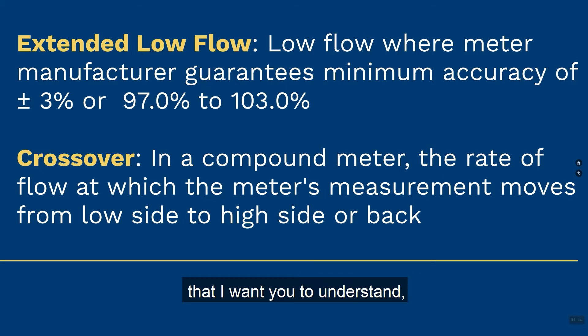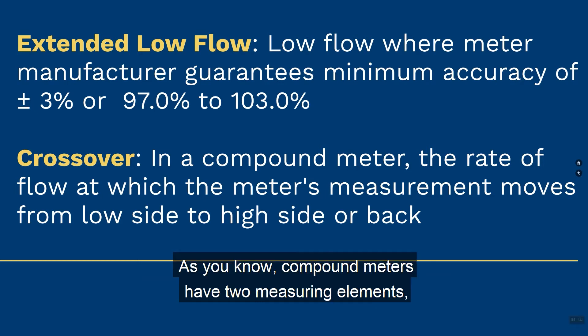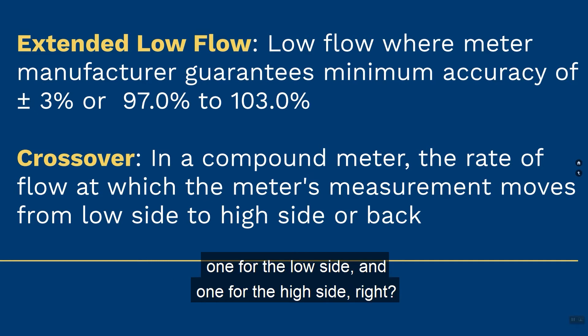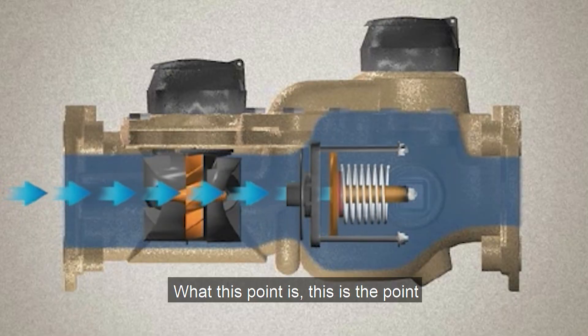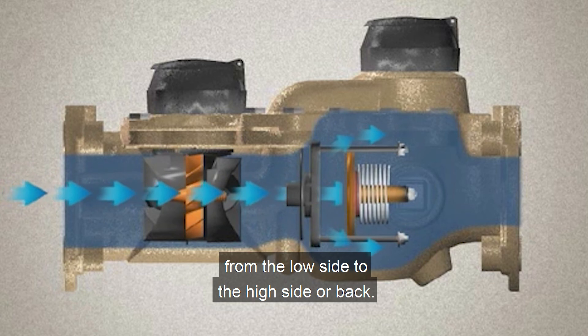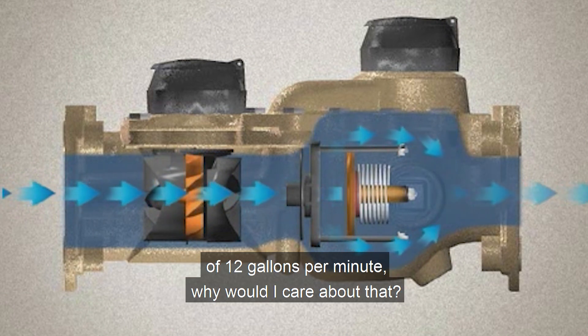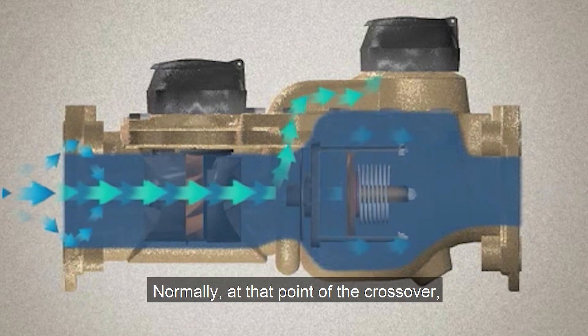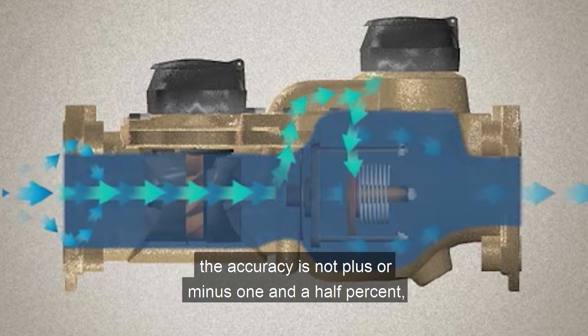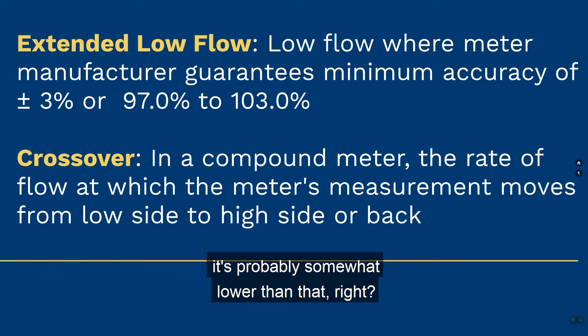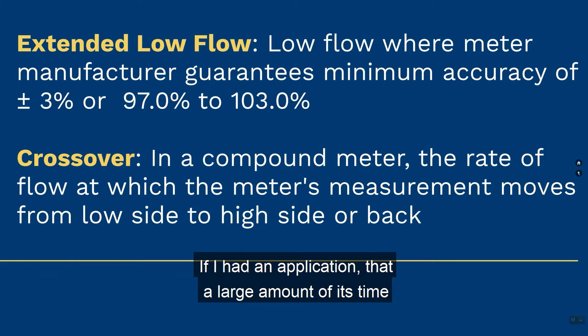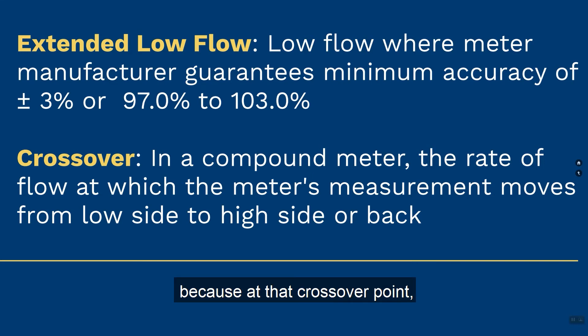The crossover point is another term to understand, and this has to do with compound meters. Compound meters have two measuring elements — one for the low side and one for the high side. The crossover point is where the meter's measurement transitions from the low side to the high side or back. At that crossover point, accuracy is not plus or minus one and a half percent — it's somewhat lower. If a large portion of an application's time is running near the crossover point, I might select a different meter because I won't have plus or minus one and a half percent accuracy there.